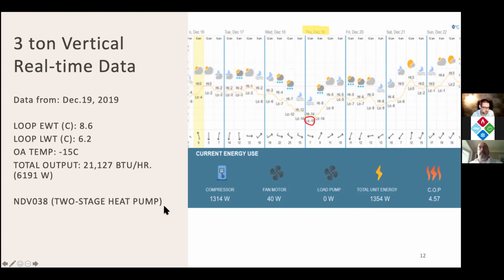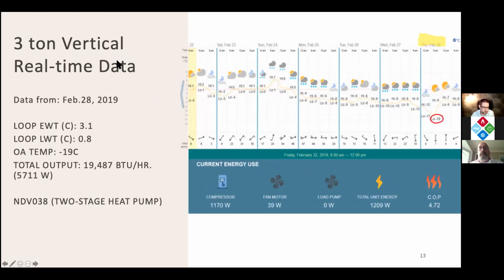If we move to a little bit later in the wintertime, now I believe this was the coldest day in that area, minus 19 degrees Celsius on February 28th. So later in the wintertime, what's happened to the loop? Well, the loop temperatures have now come down because we've been extracting heat from them for the last couple of months. So there's still our temperature difference there, outdoor air temp, and then the output from the heat pump. And again, our COP is performing quite well at 4.7.